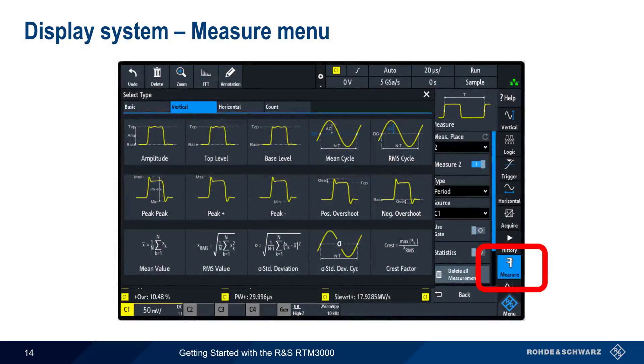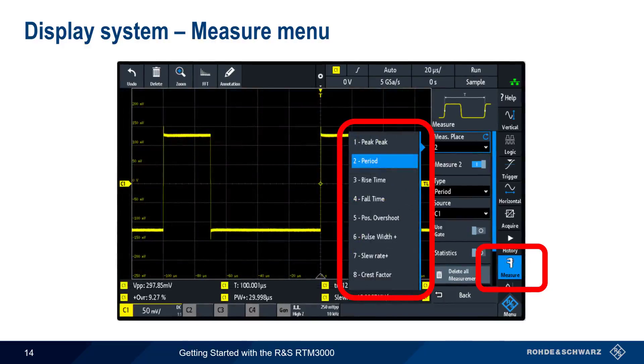On the RTM3000, there's also a measure menu, which enables an enormous range of automated measurement types in four different categories. Up to eight of these measurements can be selected and displayed at any one time. In many cases, this provides a substantial improvement over manual or marker-based measurement.